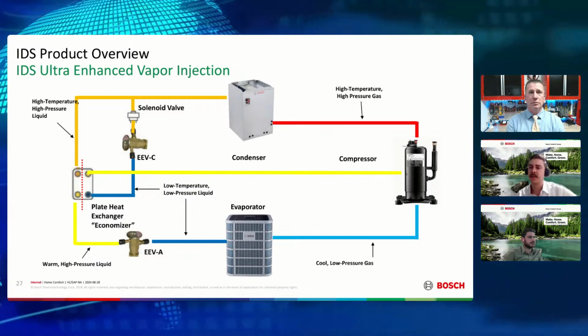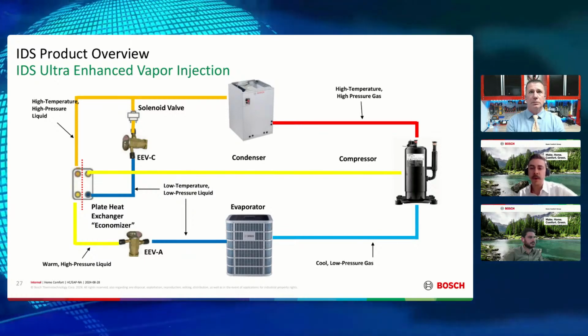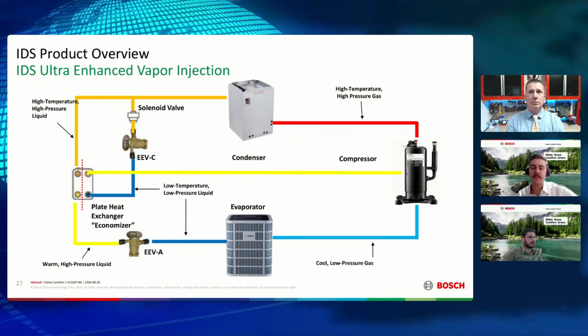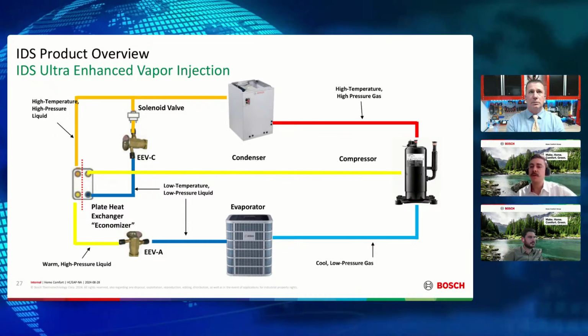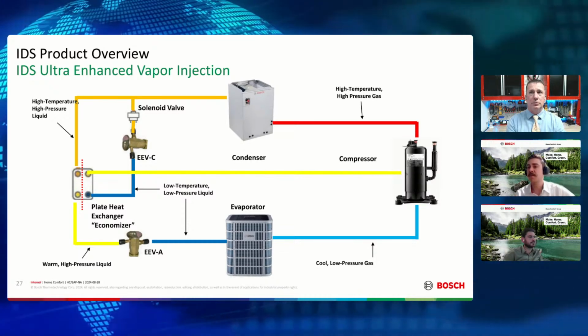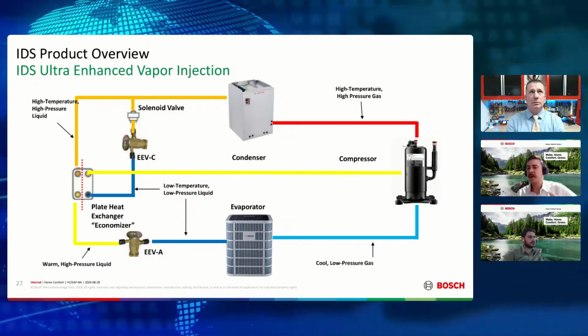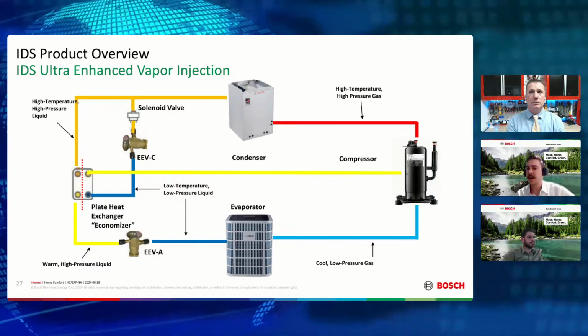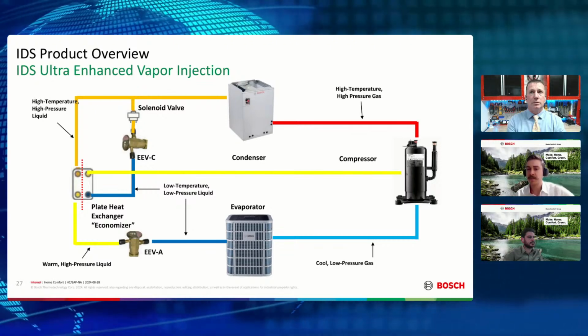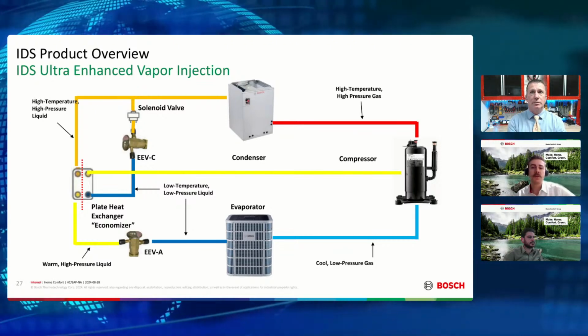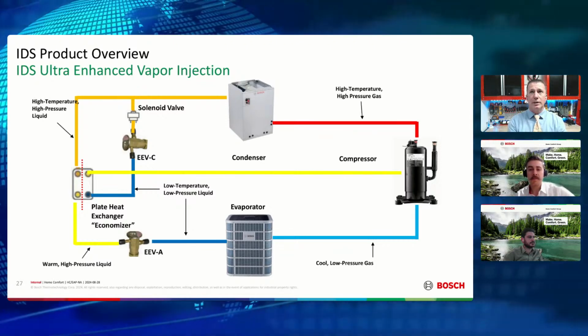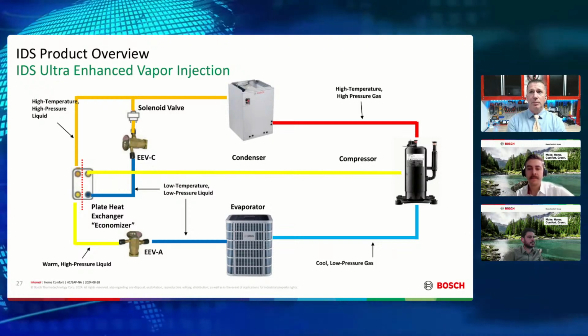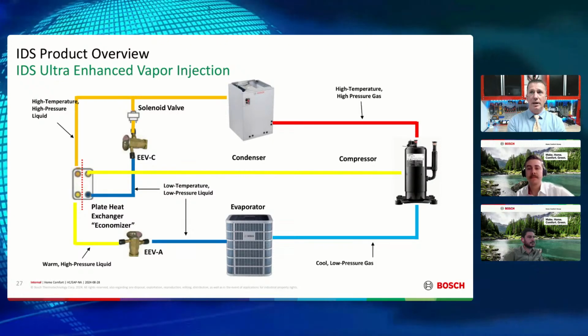So we're going to close that solenoid valve for the cooling mode, but also at certain temperatures when running the heat pump, you don't need that extra capacity, right? We talked about it before. You're not necessarily going to be running at 100% duty cycle for the inverter. Exactly. At moderate temperatures, you're not going to need it. If I don't need it, I'm just running like a high SEER heat pump until I need the extra capacity.